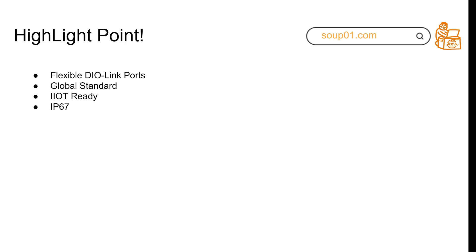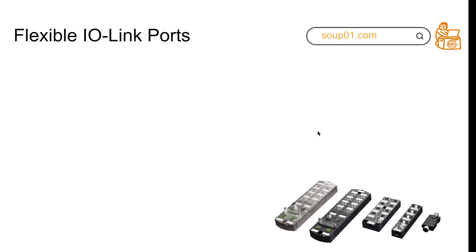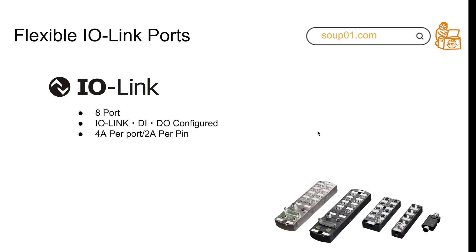Their modules all have IP67 protection. For the IO-Link ports, they have eight ports per module, and each module can be software-configured as IO-Link, digital input, or digital output. They have high current output - each port can output 4 amperes, and each pin maxes out at 2 amperes.